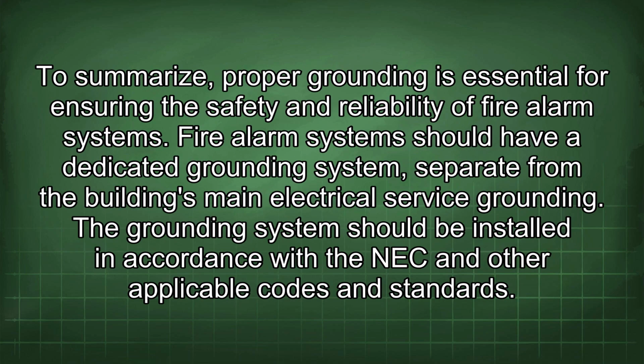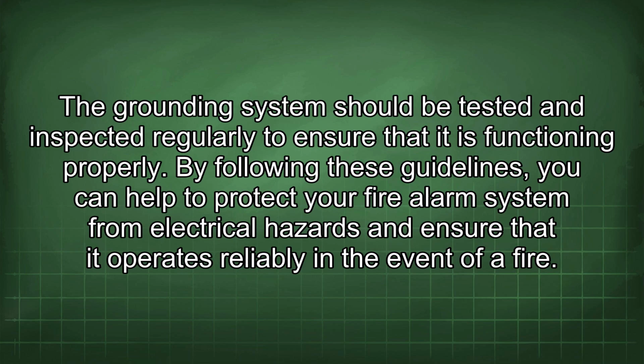To summarize, proper grounding is essential for ensuring the safety and reliability of fire alarm systems. Fire alarm systems should have a dedicated grounding system, separate from the building's main electrical service grounding. The grounding system should be installed in accordance with the NEC and other applicable codes and standards. The grounding system should be tested and inspected regularly to ensure that it is functioning properly. By following these guidelines, you can help to protect your fire alarm system from electrical hazards and ensure that it operates reliably in the event of a fire.